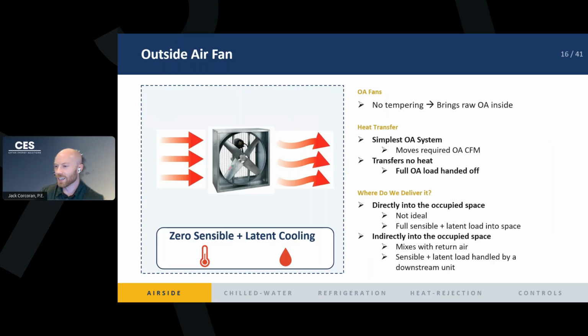It doesn't really temper the air very well. And so we can, again, dump it directly into the space. That doesn't really help us with cooling or heating it up, right? It just becomes the temperature of the outside air. Or we can dump that into a return air mixing box with a mixed air temperature, and then we just pass that load on to another coil downstream.